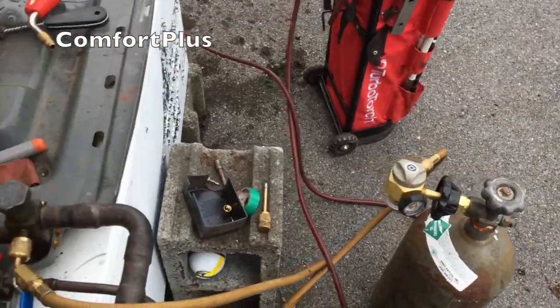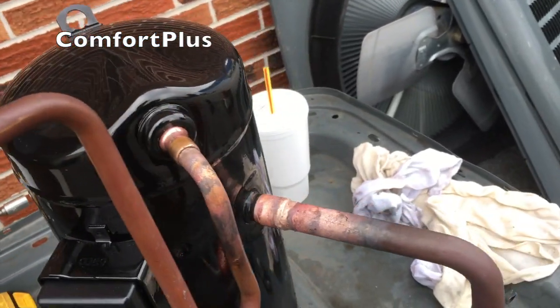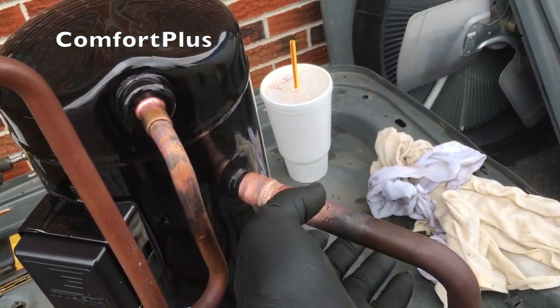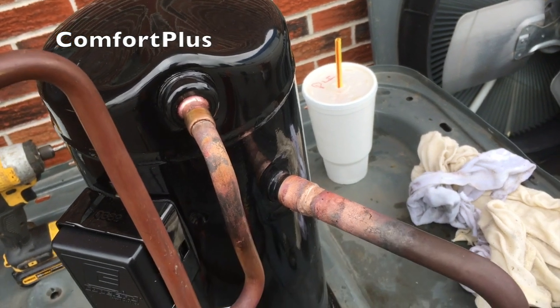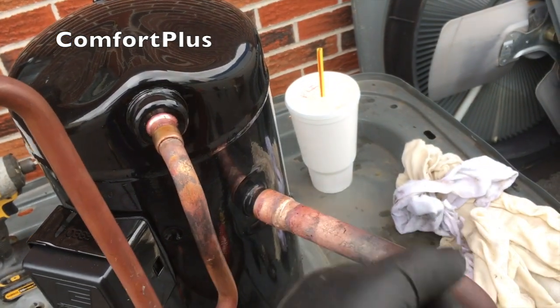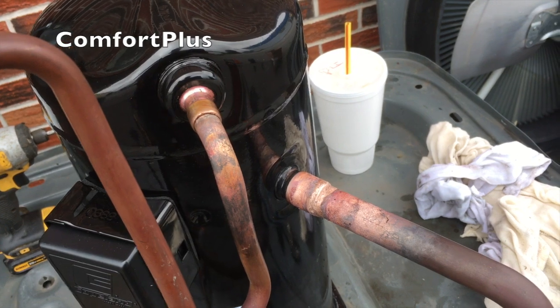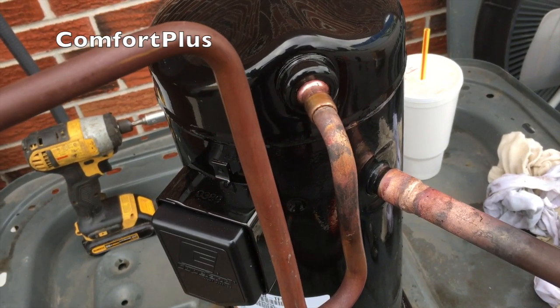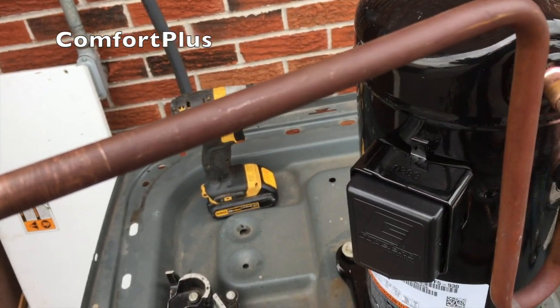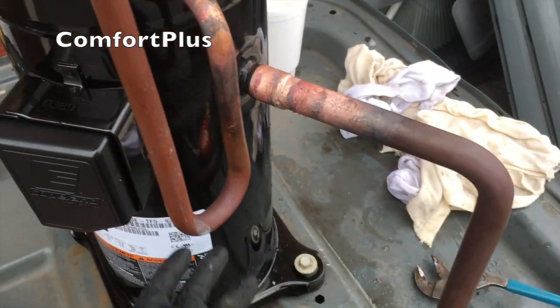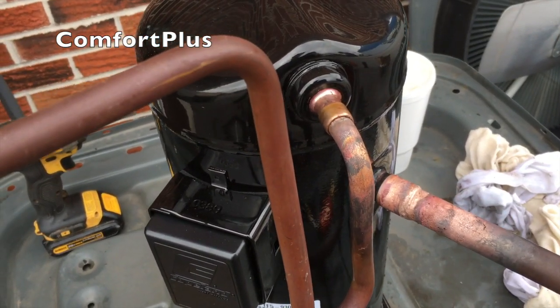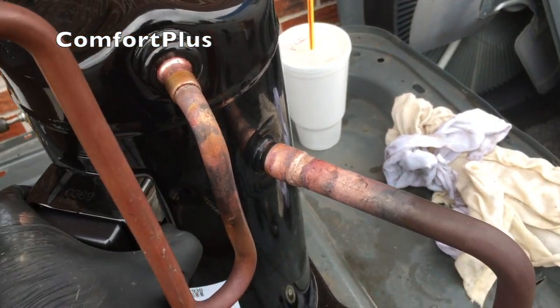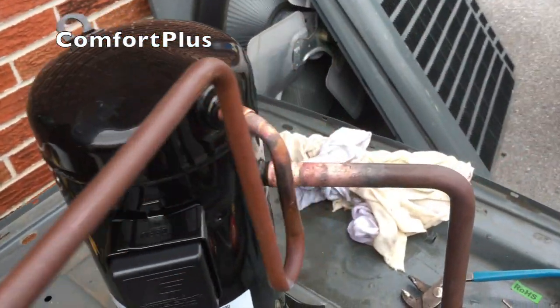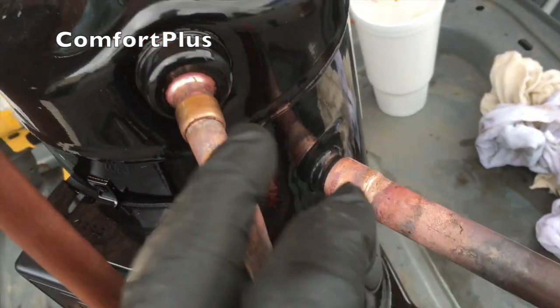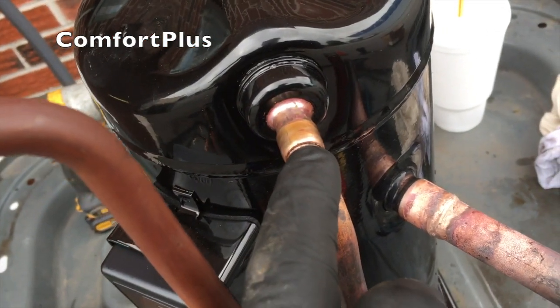Okay, I've been purging nitrogen since I started to braze the compressor in. What I did, I had nitrogen flowing out this suction line. I set the compressor up here, pulled the plugs, immediately stuck it onto the suction line, so nitrogen has been coming out, and I'll actually leave the nitrogen flowing until I get everything hooked back up, to keep this oil away from any atmosphere, absorbing any moisture, hopefully. So I've got the suction line brazed in. I'm going to braze in this discharge line.